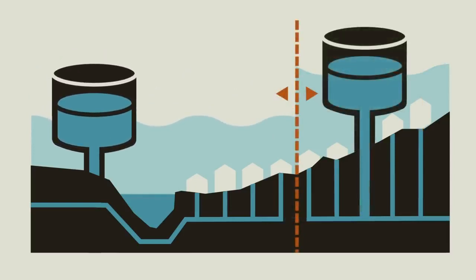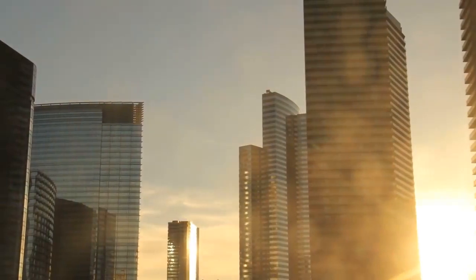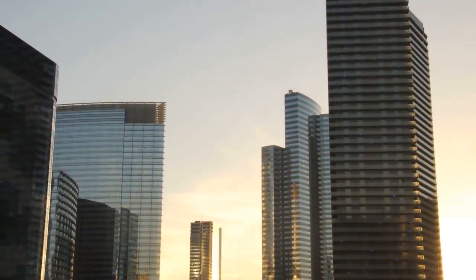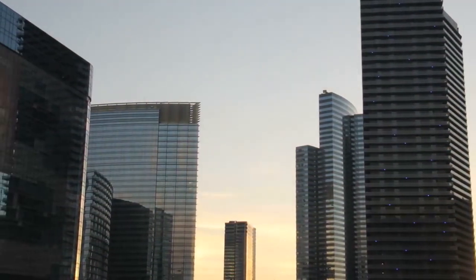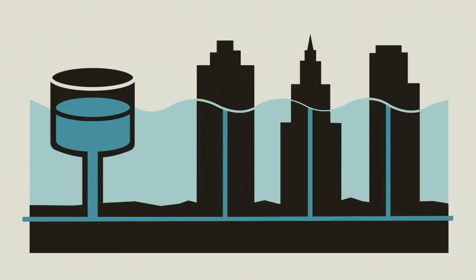To solve this challenge, many large cities maintain separate distribution systems called pressure zones, each with their own water tower, to serve customers at different elevations within the city. But what happens if you need to serve customers at different elevations in the same location? Tall buildings like skyscrapers can have adequate water pressure on the lower floors, while the higher floors can go up near the surface or even above the virtual ocean in the water distribution system. So instead of relying on city water pressure, most tall buildings use their own pumps to provide water to the upper floors. And some cities like New York even require that each building have its own elevated storage tank.